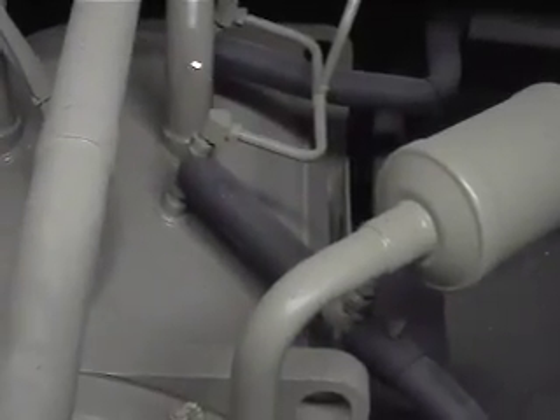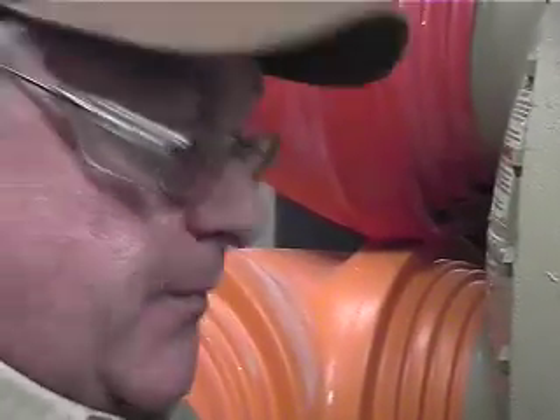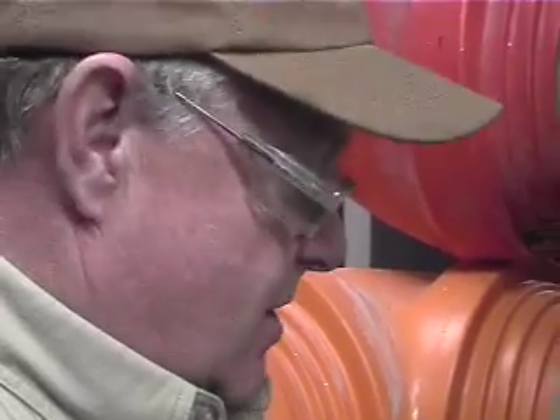Something that I didn't bring up when we was in classes, we've got what we call dual eductor tees. These dual eductor tees create a pump. It's actually a pump. It takes your high pressure off of this line right here, it comes down and it creates a pump. The purpose of these dual eductors is it'll take your liquid refrigerant off the evaporator and off your suction cover and return it back to the oil sump. So it's returning refrigerant and oil as it mixes. As the oil heater in the oil sump heats up, it boils off that refrigerant. So what you have left is a full supply of oil.